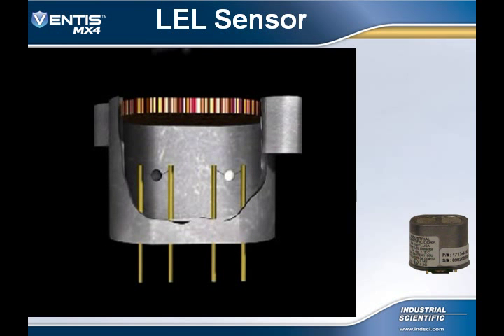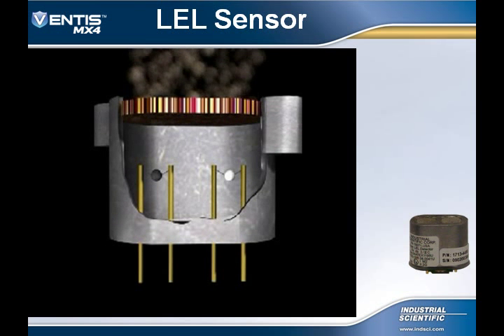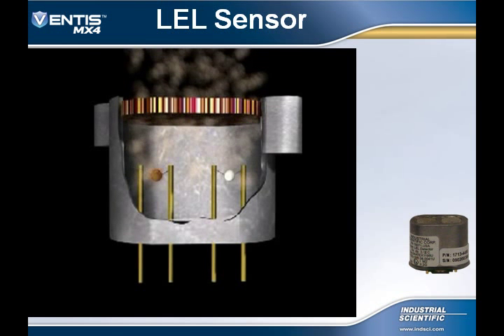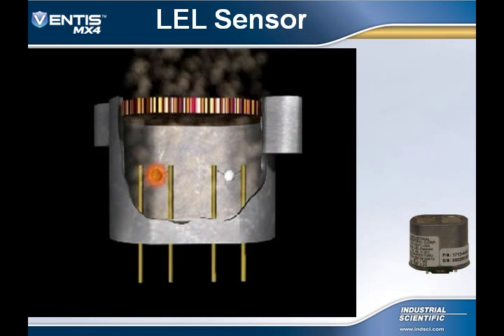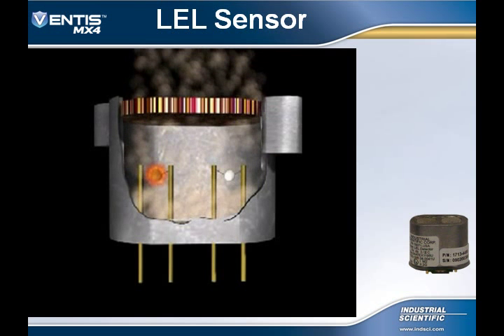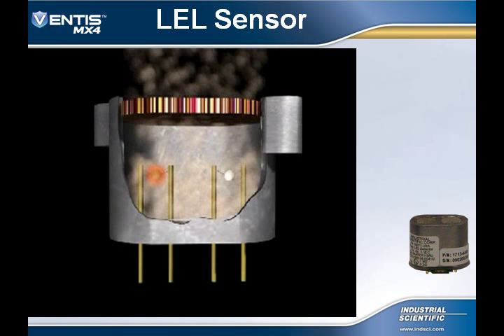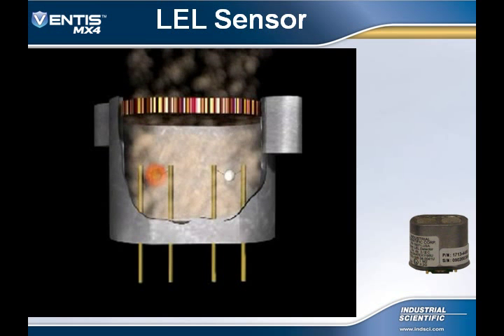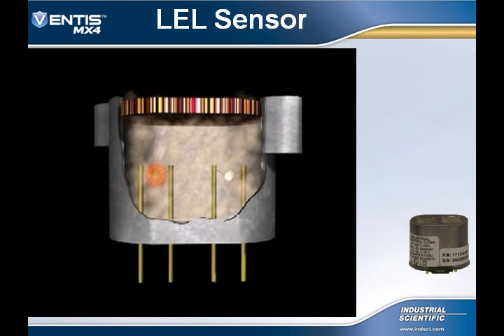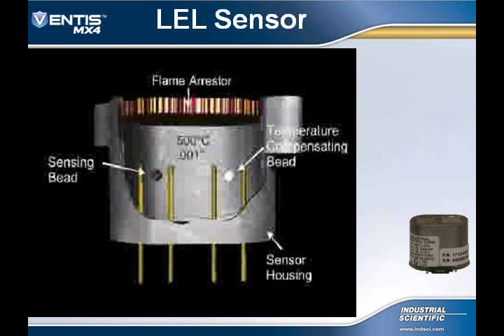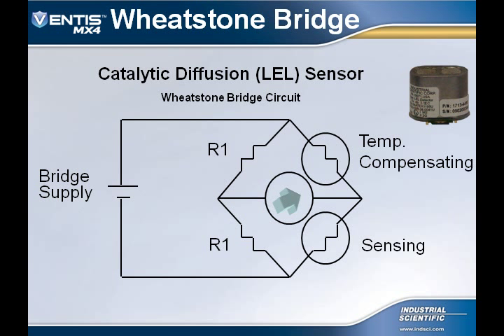Once the combustible gas enters the sensor, the sensing bead will start to burn the combustible gas on its surface. This action increases its temperature, which in turn increases its resistance. Even though the combustible gas is entering the sensor, the temperature compensating bead will stay the same. The change in resistance between the 2 beads is what will be measured. That measurement of change in resistance is done by utilizing the Wheatstone bridge circuit in the instrument, which is then converted to LEL readings.